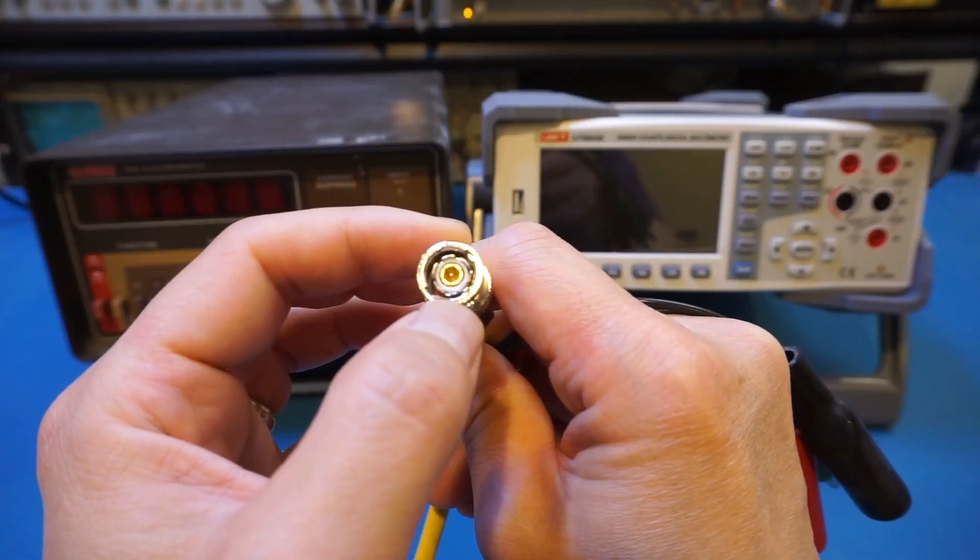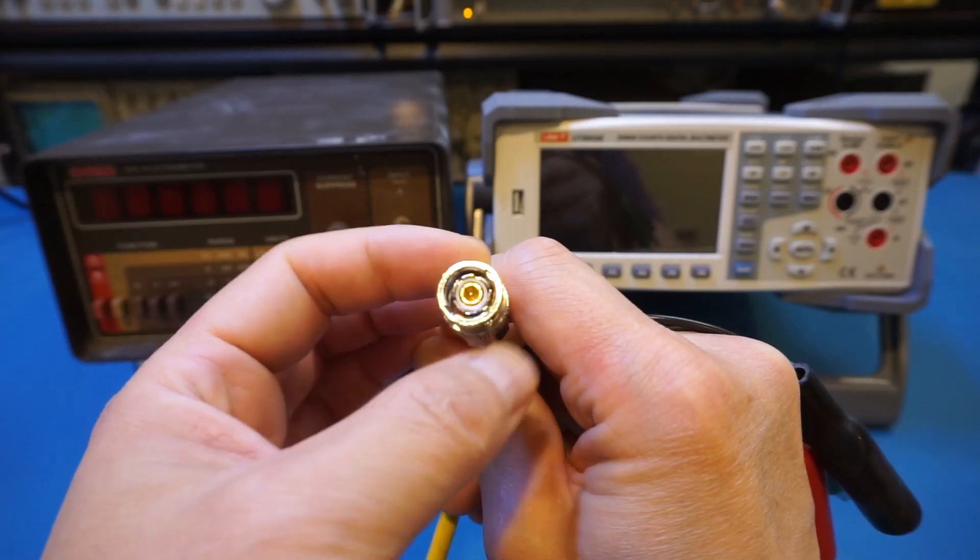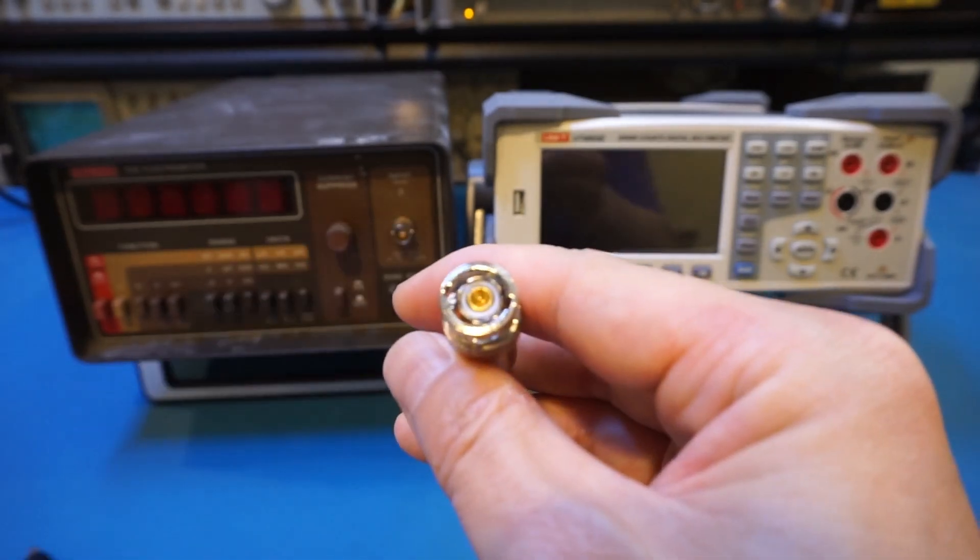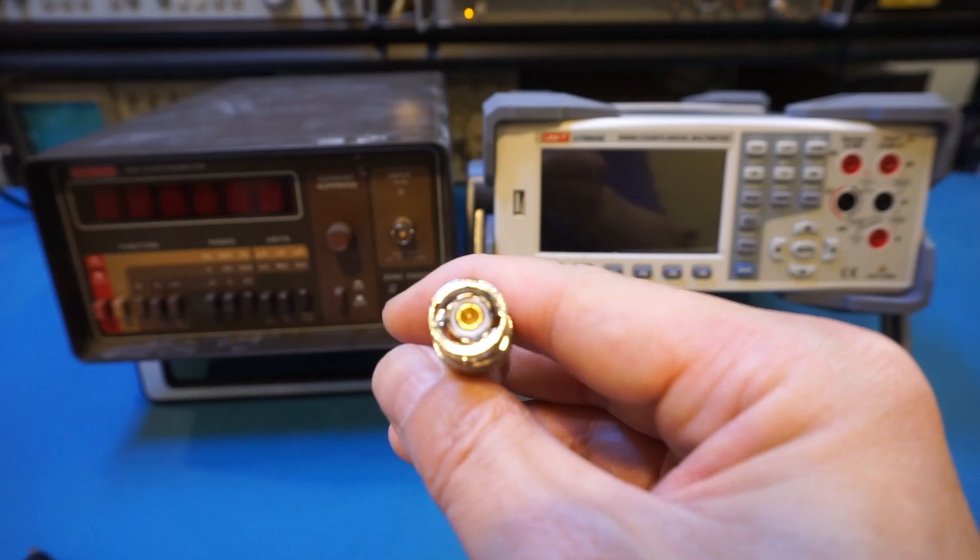You can see this is not your ordinary cable. It has not only the outer shielding, it has also an inner shielding. And that inner shielding is essentially the guard, which surrounds the inner conductor.